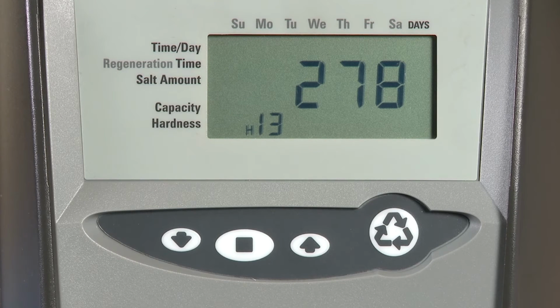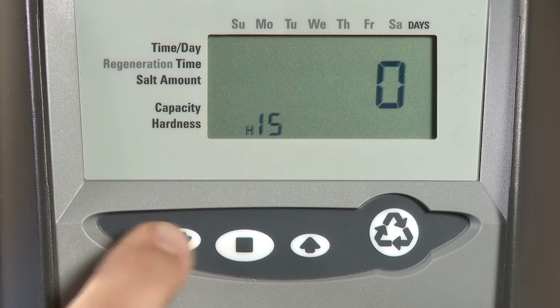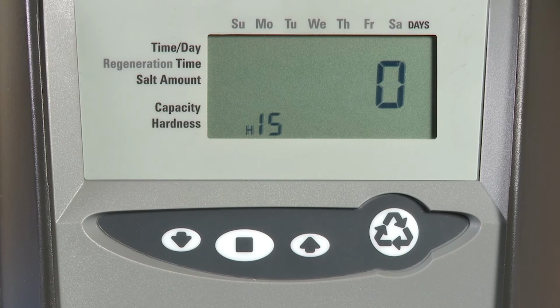This will adjust based on your actual water usage, but you can see that this is our initial calculation based on 30% reserve capacity. H14 is going to be our average service cycle from 0 to 255 days. H15 gives us what the peak flow rate is from 0 to 200 gallons per minute, or up to 1,000 liters per minute.